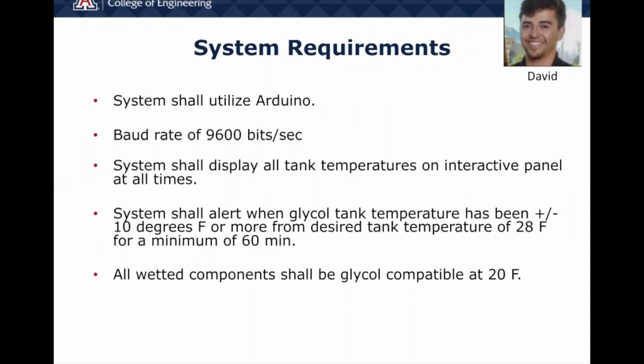Its baud rate shall be 9600 bits per second. It shall display all tank temperatures on an interactive panel at all times. There shall be an alert when a tank temperature is above or below 10 degrees Fahrenheit of a desired temperature of 28 degrees Fahrenheit for a minimum of 60 minutes, and wetted components shall be glycol compatible at 20 degrees Fahrenheit.